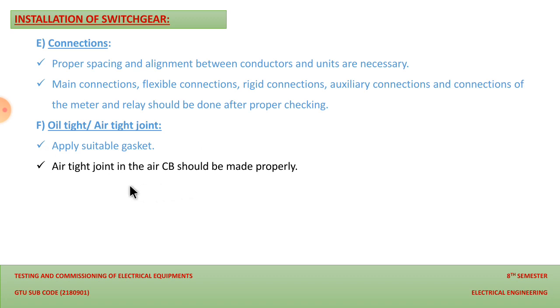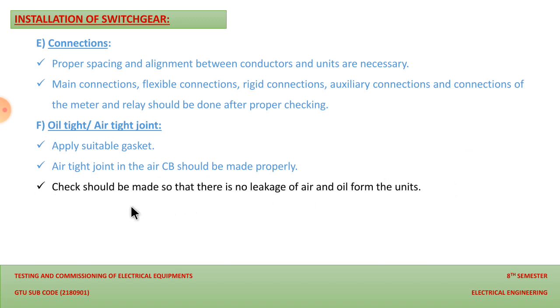Then airtight joints in the circuit breaker should be made properly, because if air enters inside the switchgear, and if the air is moist, then that can produce corrosion between the moving parts. So yes, we need to protect our device from contaminated air. So we have to provide a proper gasket to provide proper insulation from the air. The check should be made so that there is no leakage of air and oil from the unit. That is the most necessary point that we have to check after we have done proper erection of the switchgear.